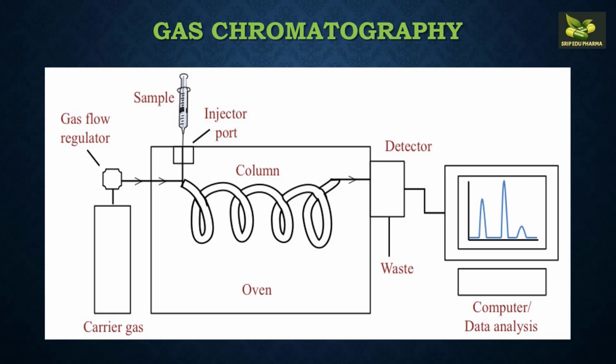Normally TCD, the thermal conductivity detector, is useful, and this detector is analyzed in terms of a Wheatstone bridge network. The response of the reference, or rather you can say the standard one without sample, and the other one, the sample detector, are both read by the Wheatstone bridge network, and these impulses are diverted towards the computer.